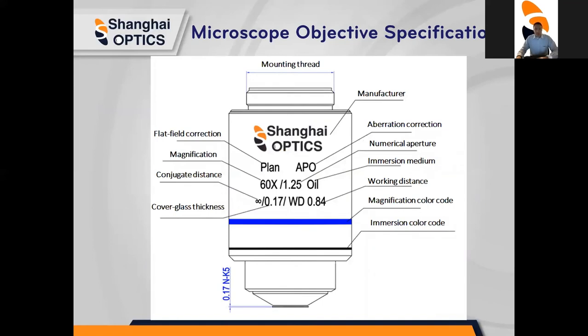You can always find the specifications of an objective lens on the lens barrel. This includes the magnification, aberration, numerical aperture, and many more. When you look at the objective lens, we see the magnification of 60x, an infinity symbol which tells us this is an infinite conjugate objective, and we know the resolution based off the numerical aperture of 1.25.